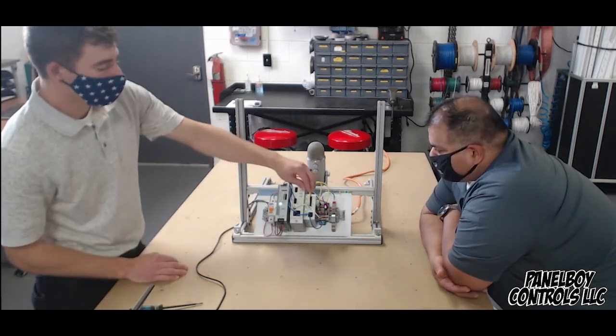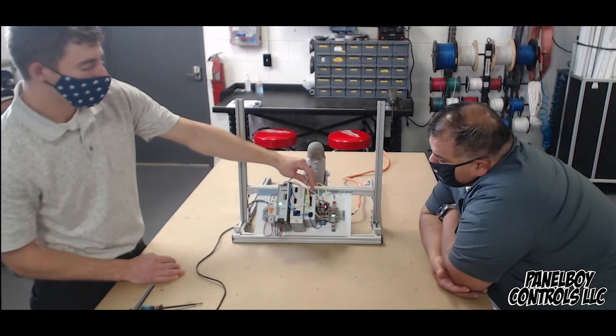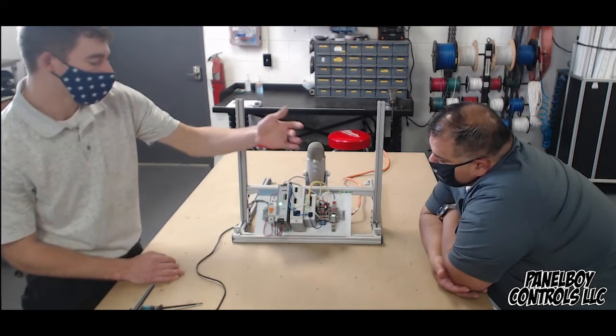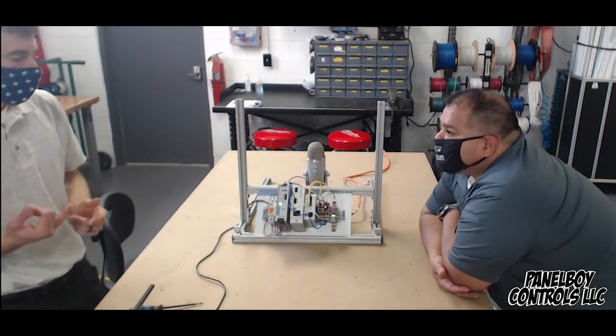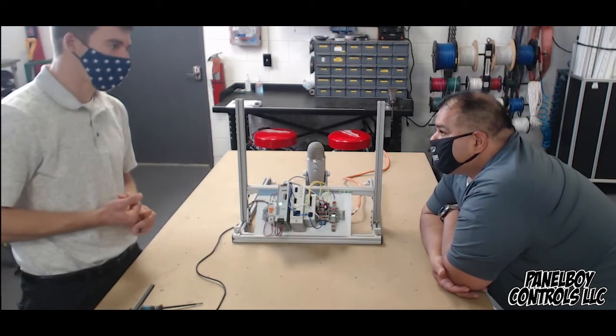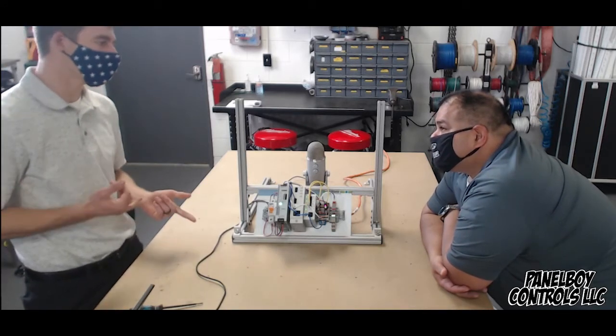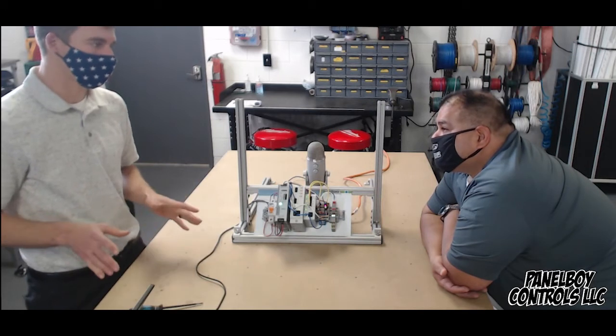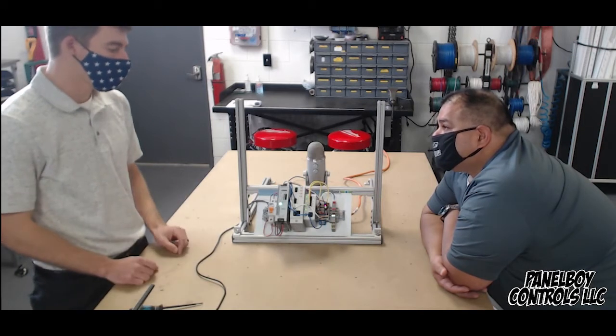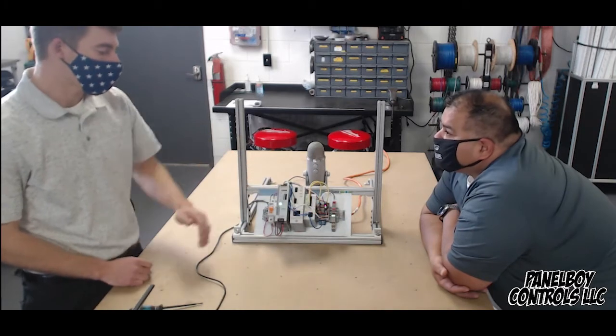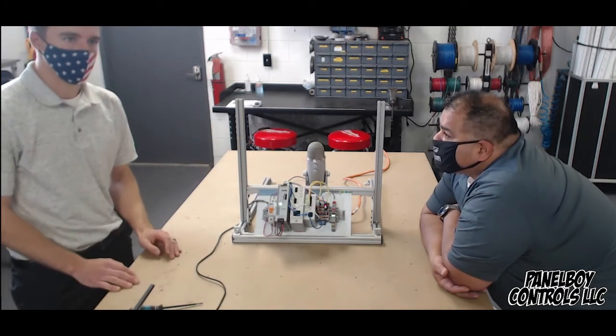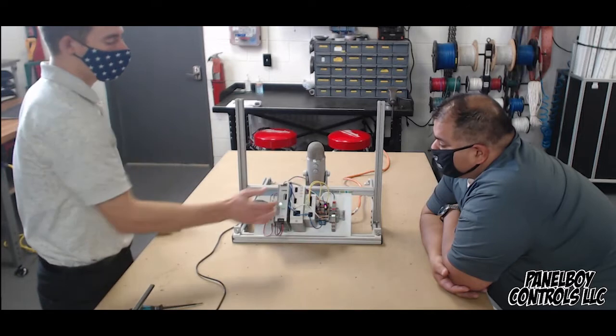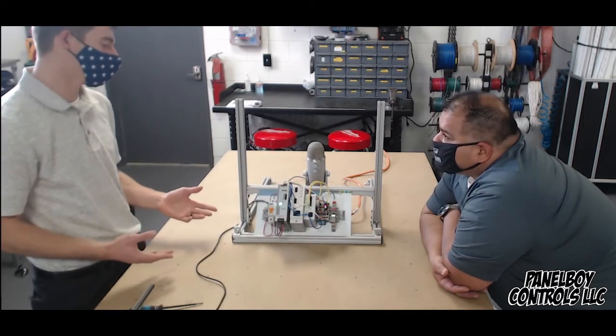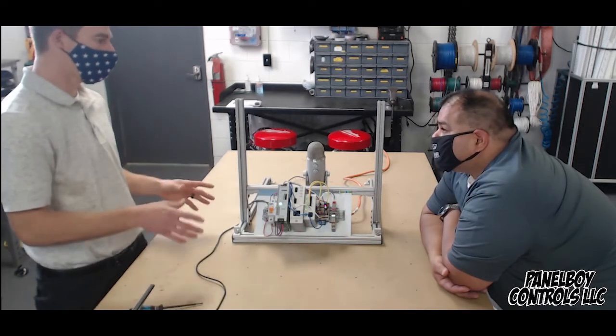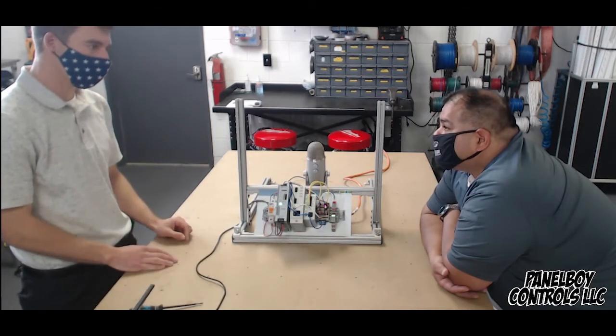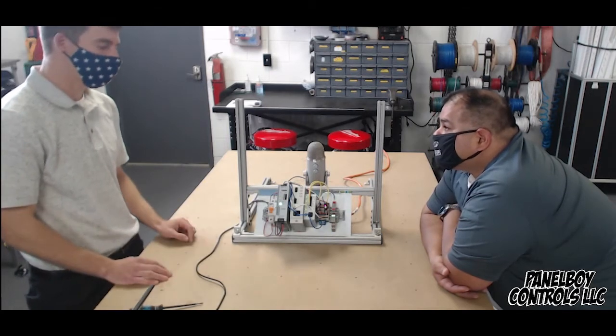The diagnostic information you get out of IO Link is a lot more than just signal and reset. You can get information like what a channel is saying, what the current draw is, or reset it using your HMI or preset setup if something goes bad. One of the biggest advantages of IO Link is if I drop in another IO Link solution, it pulls the configuration from the master and you're up and running again. Pretty cool stuff.